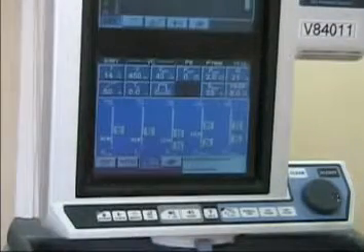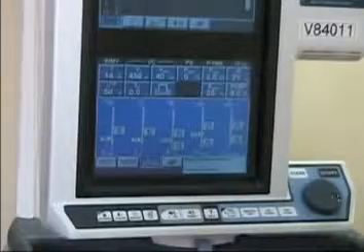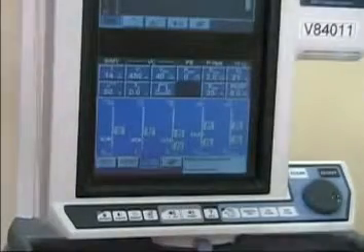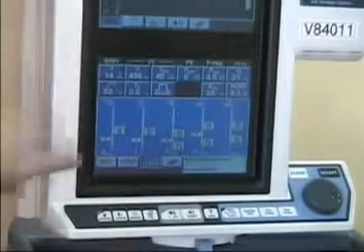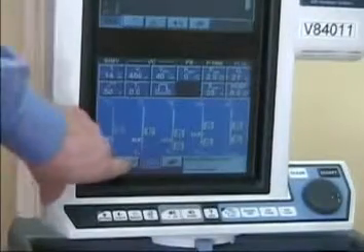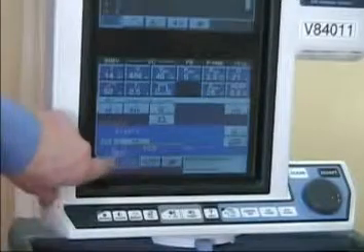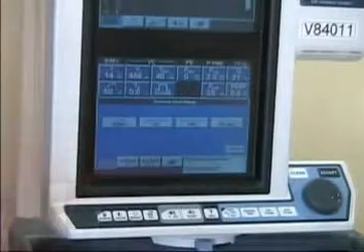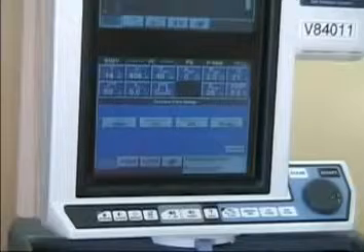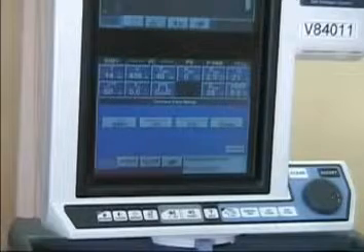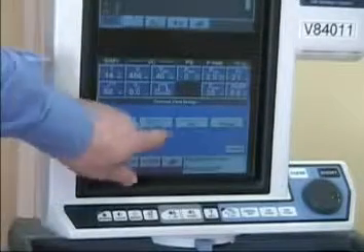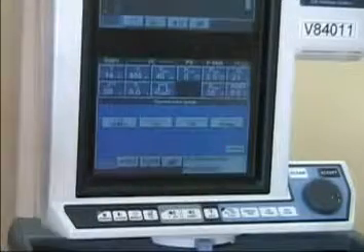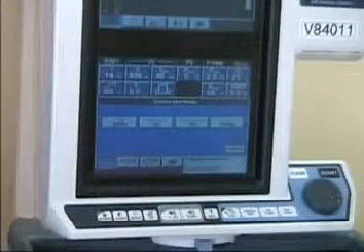That completes the majority of the setups. You can also set up your apneas, apnea ranges if you need that. You can go back and adjust the settings, the modes, the volume control or pressure control, pressure support, and even easily switch over to flow triggering.